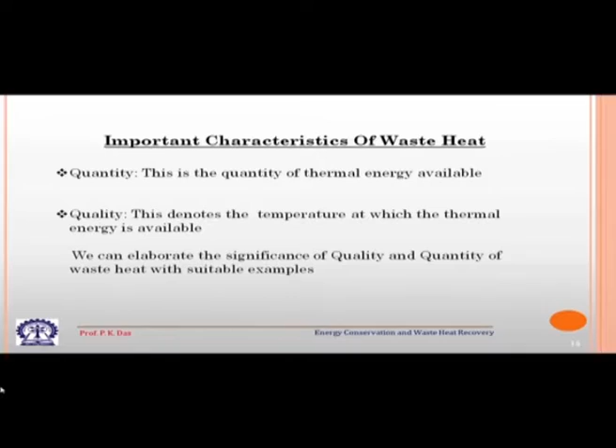Quality gives us flexibility of selecting methods, and enables us to select better methods for exploiting waste heat. But in quality there is something else also. If temperature is the physical quality, there is also a chemical quality of the waste heat, particularly when we are dealing with exhaust gases. The exhaust gases could sometimes be very obnoxious. They may have components which are corrosive, which can create fouling, which are loaded with particulates. So, if taken into a device, they will erode the device and damage its surface. So, this chemical quality is also very important.